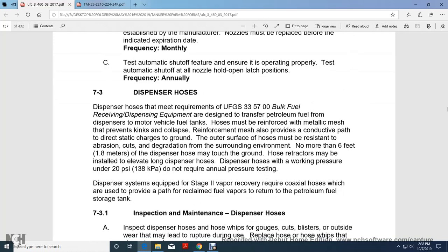7.3 Dispenser hoses. Dispenser hoses meet the requirements of Unified Facilities Guide Specification 33 57 00, bulk fuel receiving and dispensing equipment, designed to transfer petroleum fuel from the dispenser to the motor vehicle fuel tanks. Hoses must be reinforced with metal mesh, which prevents kinking and collapse. The reinforcement mesh also provides a conductive path to direct static charges to the ground. The outer surface of the hose must be resistant to abrasion, cuts, and degradation from the surrounding environment.